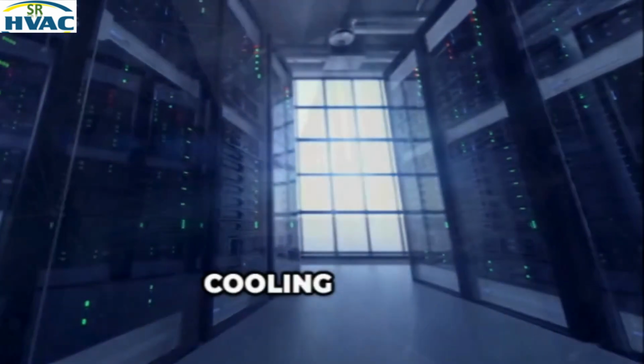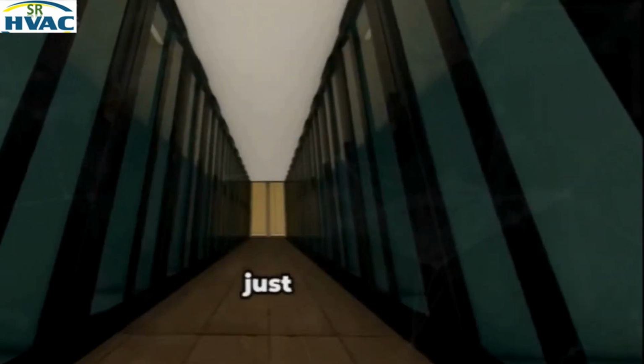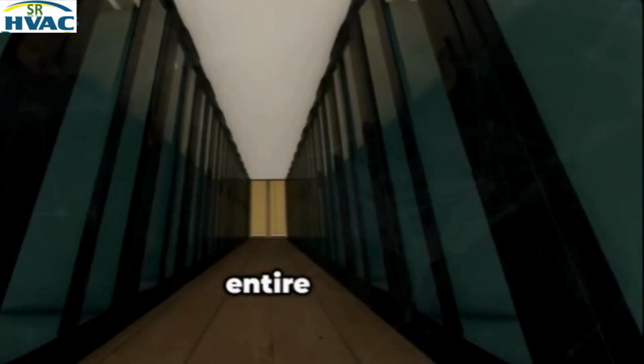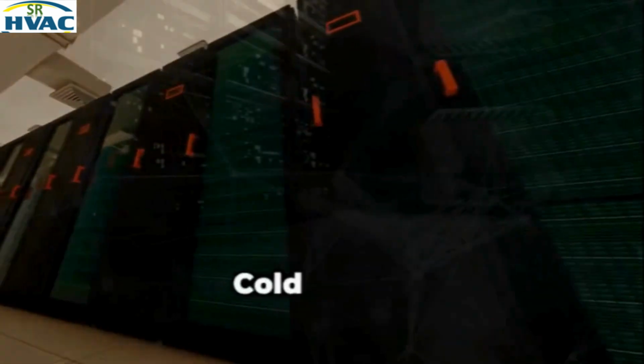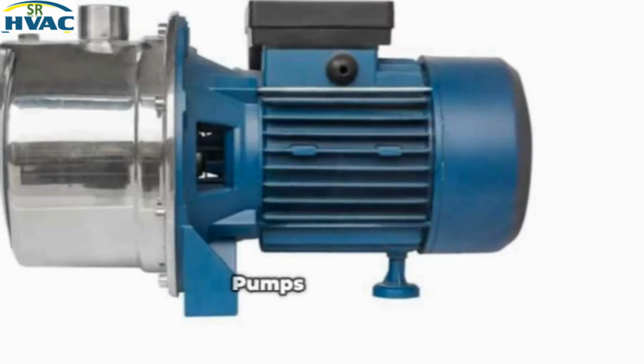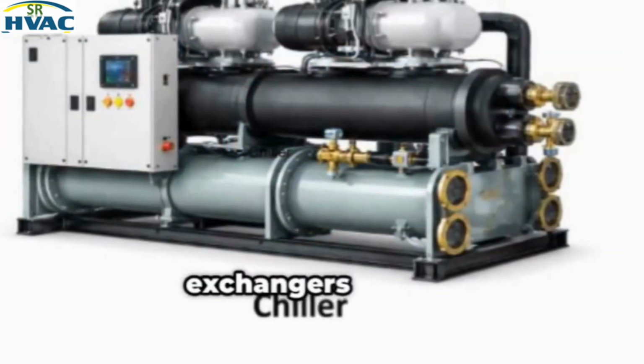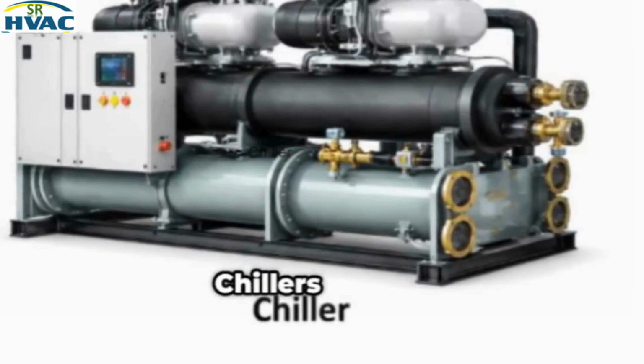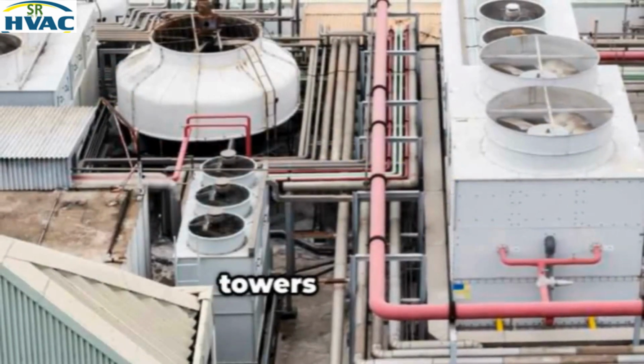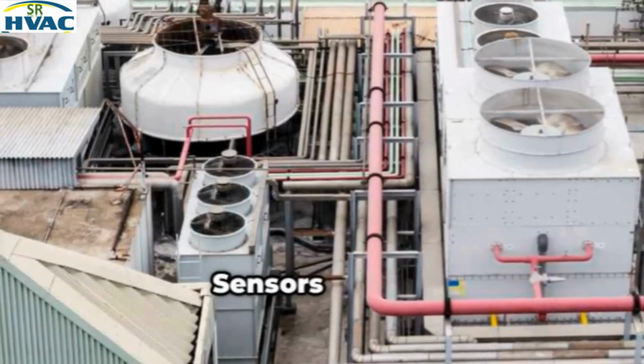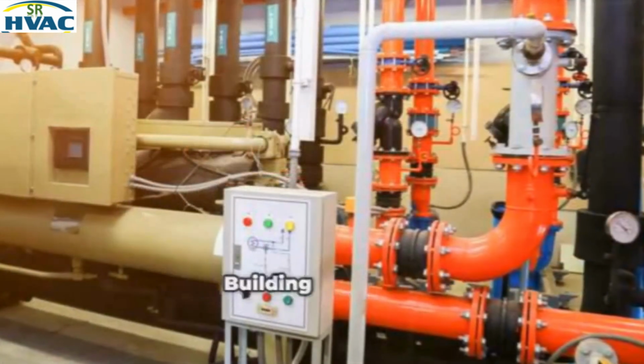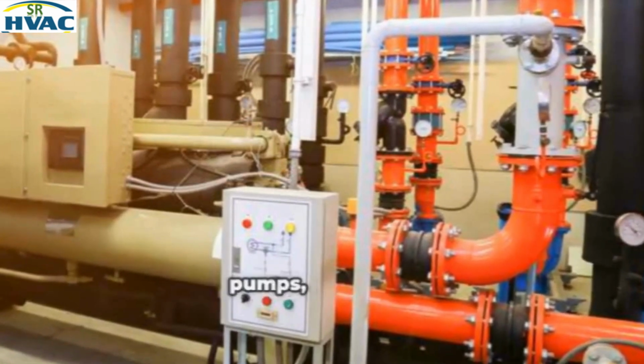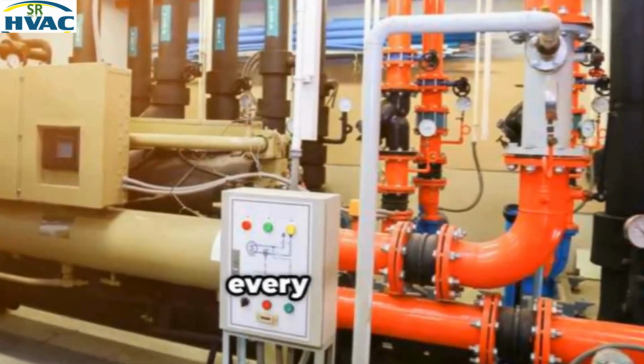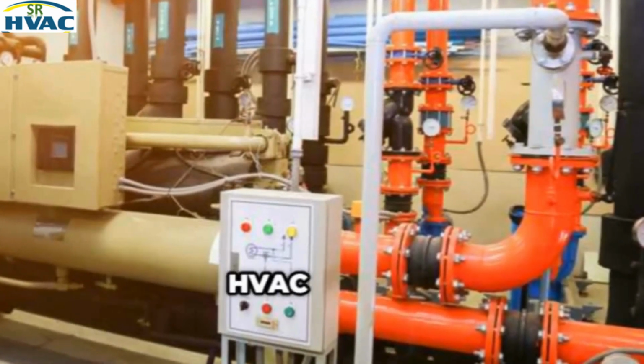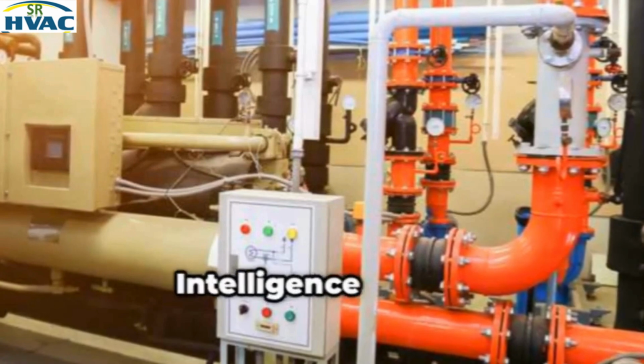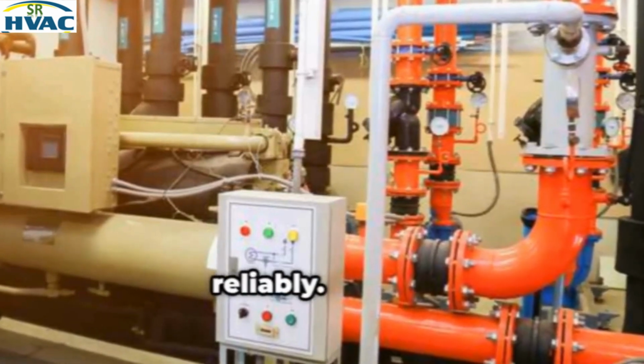Chapter 5: The Complete Cooling System. Cooling an AI data center isn't just about the server. Behind the scenes is an entire HVAC system working together. Cold plates remove heat from the processors, pumps circulate the coolant, heat exchangers transfer thermal energy, chillers cool the circulating water, and cooling towers reject heat to the atmosphere. Sensors constantly monitor temperatures, and building management systems automatically adjust pumps, valves, and cooling equipment every second. Without this sophisticated HVAC infrastructure, artificial intelligence simply couldn't operate reliably.